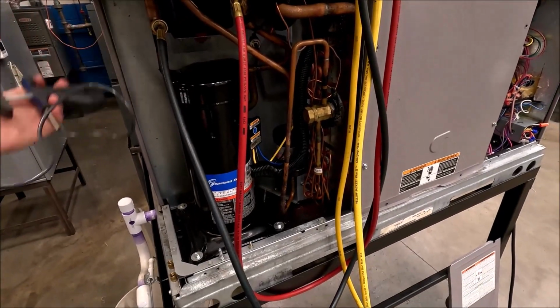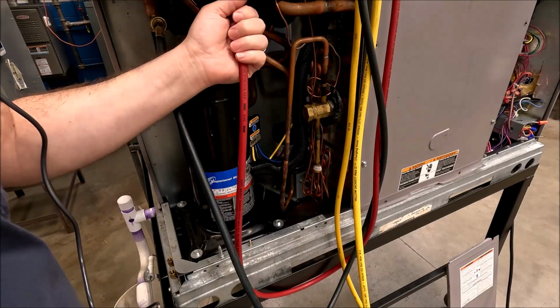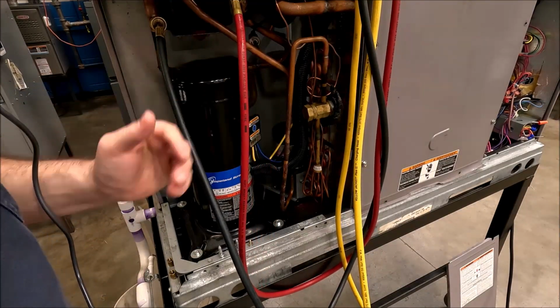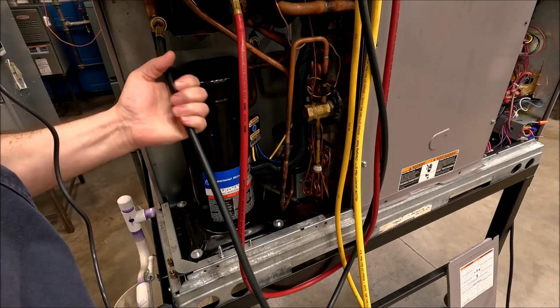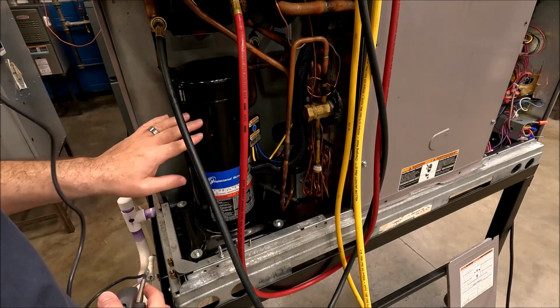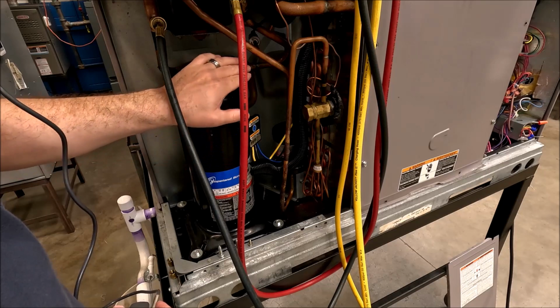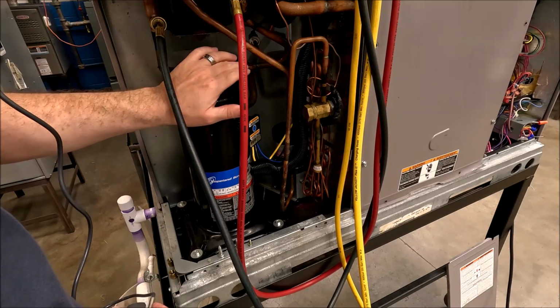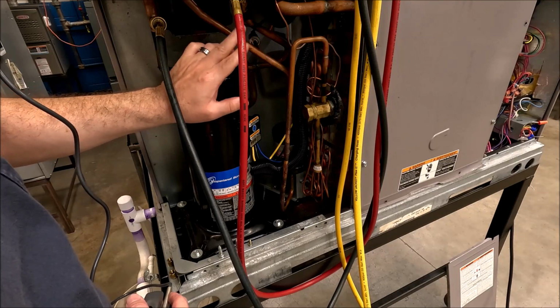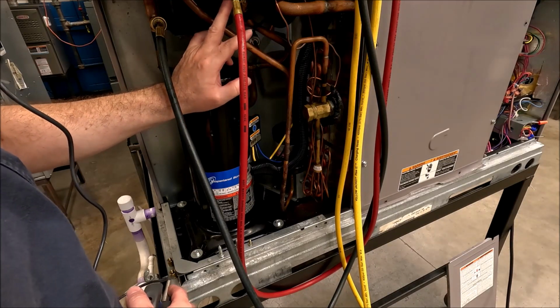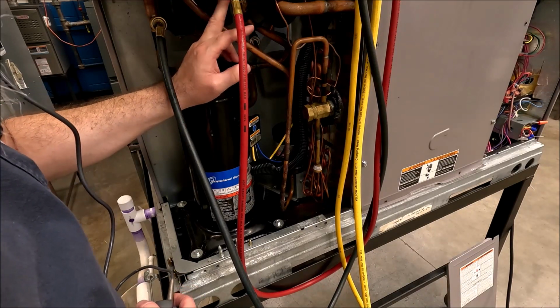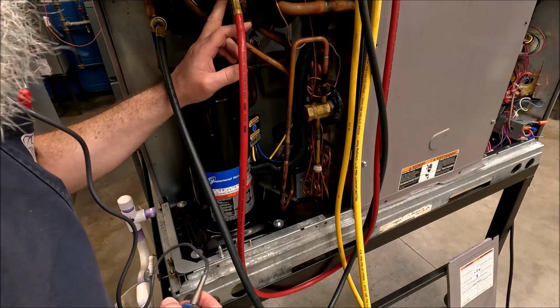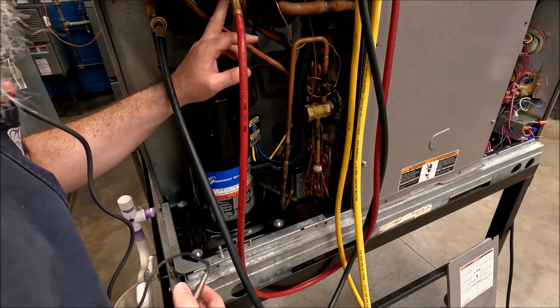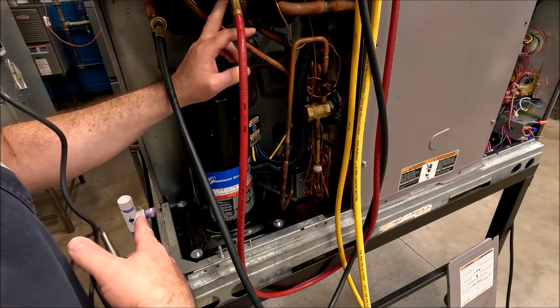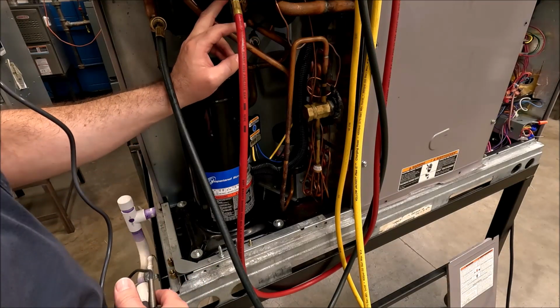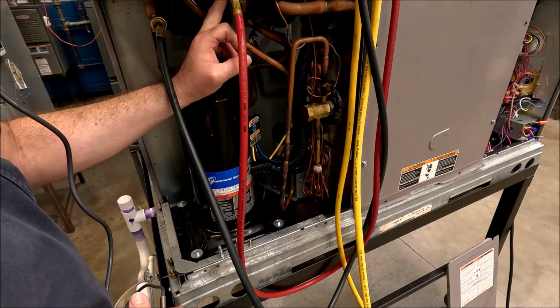Now, when you've got a package unit like this, my high side connection, a lot of people think, well, I just hook on the line where my hose goes. And you have to understand that this compressor, the line that we looked at, the discharge line's coming out of this compressor, and about 8 or 9 inches later, not even a foot, they give us an access point.